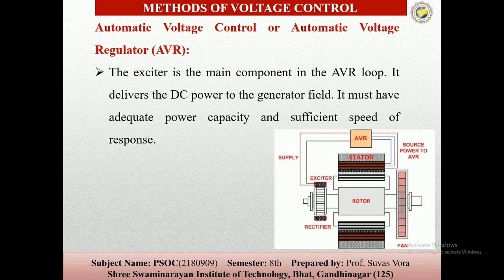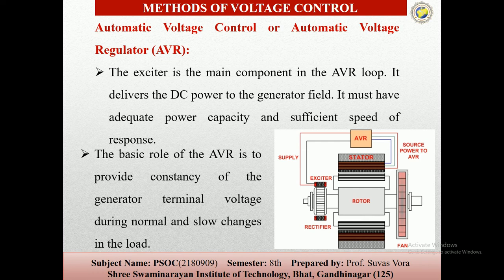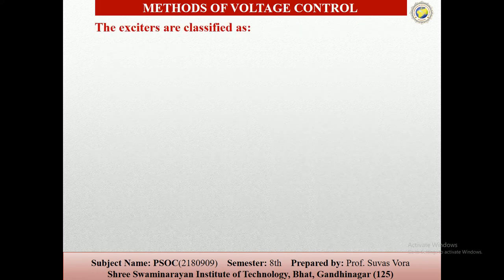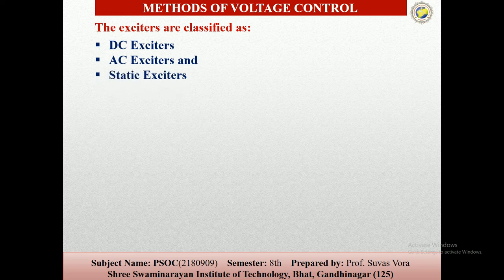So these are the AVR systems that continuously check the stator. The basic role of the AVR is to provide constant generator terminal voltage during normal and slow changes in the voltage. Depending on the type of supply given to the field winding of the alternators, exciters are classified as DC exciters, AC exciters and static exciters.